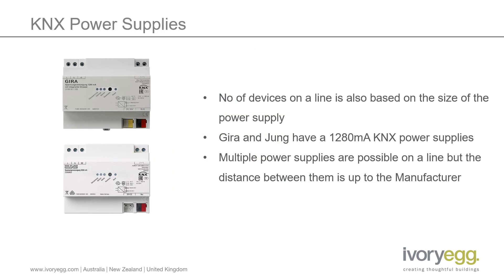Whilst this is a really big step forward and a major simplification for designing systems, the other limit on the number of devices on a line is the size of the power supply. Whilst we may be able to have 256 devices on a line, there aren't currently any power supplies that could deliver enough current, assuming the device average of 10mA each. Gira and Jung do have a 1280mA power supply, which potentially doubles the number of devices you could have over a standard 640mA power supply.